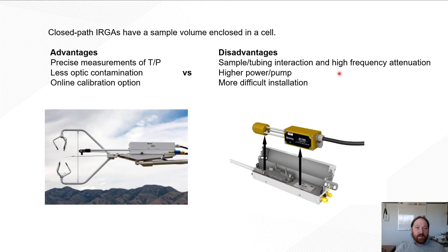So some disadvantages of that closed path is that it doesn't have as high of a frequency response as our open path. So the sample tubing and sample in tubing interaction and high frequency attenuation is a real concern. So as the air is going down that tubing, there's interaction with the walls that cause increased lag time from when the measurement was first brought into the inlet and when it is actually being analyzed by the analyzer.